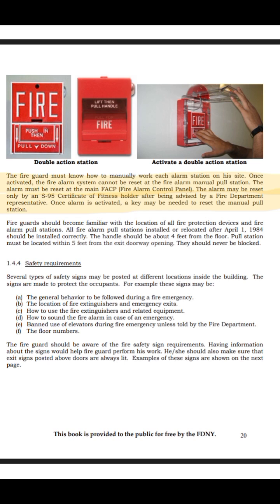Once activated, the fire alarm system cannot be reset at the fire alarm manual pull station. The alarm must be reset at the main FACP fire alarm control panel. The alarm may be reset only by an S95 certificate of fitness holder after being advised by a fire department representative. Once the alarm is activated, a key may be needed to reset the manual pull station.